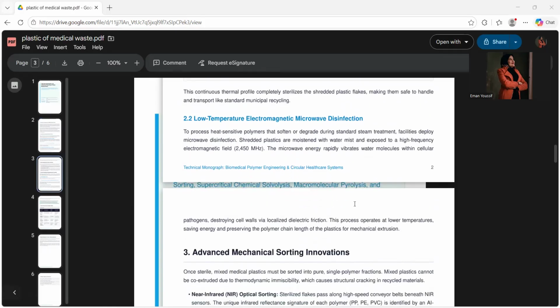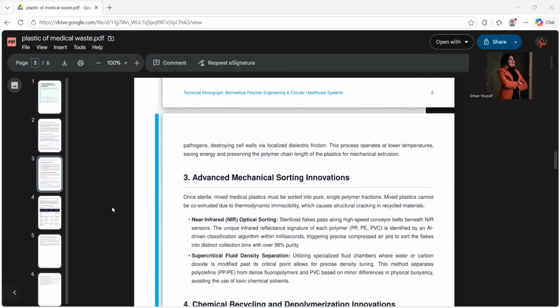Low temperature electromagnetic microwave disinfection processes heat sensitive polymers that would soften or degrade during standard steam treatment. Facilities deploy microwave disinfection, ensuring plastics are moistened with water mist and exposed to a high frequency electromagnetic field. This microwave energy rapidly vibrates water molecules within cellular pathogens, destroying cell walls via localized dielectric friction. This process operates at lower temperatures, saving energy and preserving the polymer chain length of the plastic for mechanical extrusion.